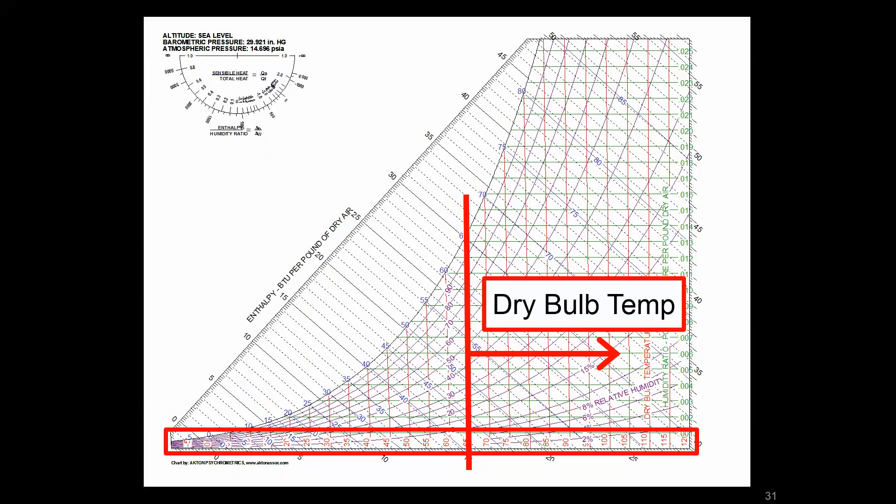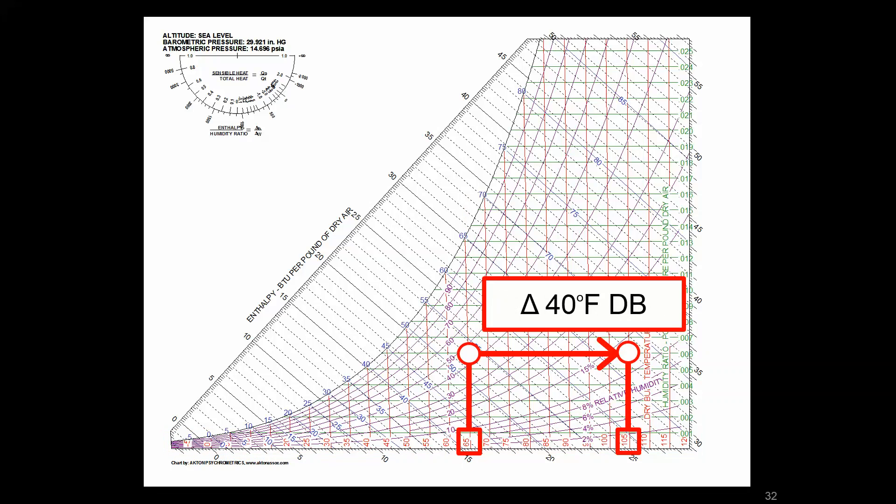The first one is the most intuitive, which is temperature or dry bulb temperature. This is that sensible temperature we can feel with our skin and measure with a basic thermometer. From left to right goes from decreasing to increasing temperature. Any points on a vertical line have the same dry bulb temperature. In this example, we're going from 65 to 105 degrees Fahrenheit, a delta of 40 degrees Fahrenheit dry bulb temperature.